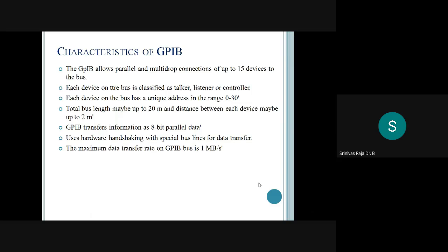The total bus length may be up to 20 meters. GPIB transfers information on 8-bit parallel data and uses hardware for handshaking with special bus lines. The maximum data transfer rate is up to 1 MB per second. This gives wide capacity to transmit and receive data, and to control devices remotely — from the PC you can transmit and receive data from devices using the GPIB interface and also control a remote device.